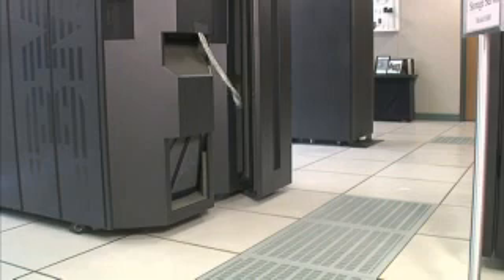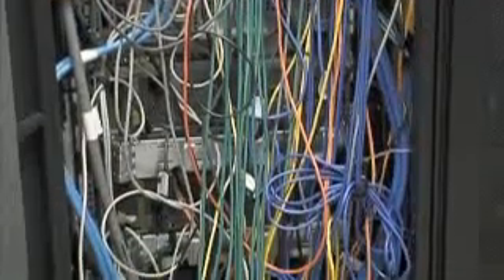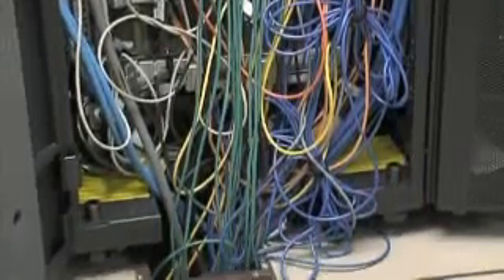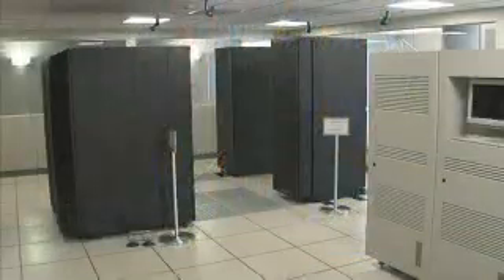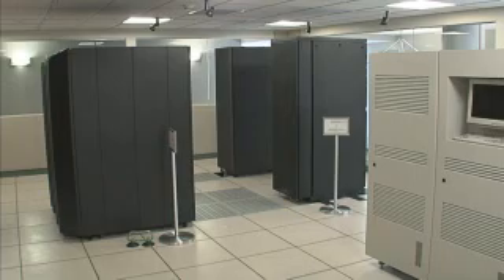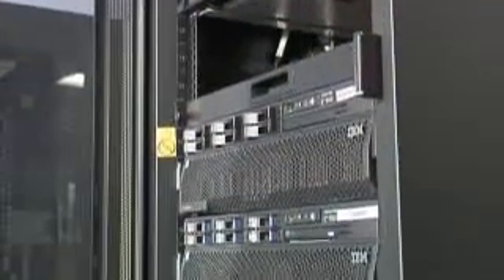Once we started analyzing the floor, we realized that by laying it out as a showroom, we had inadvertently created a lot of bad practices. The rows of machines in the front were actually exhausting heat into perforated tiles in the back, where additional machines would then try to use that for cooling. In addition, we had done poor cable management as well as other things in the raised floor itself. The racks were not laid out correctly. We had gaps in the racks in between them, as well as in between the machines in the racks. What this did was it allowed for the air to intermix from the front to the back, and this is what gave us a room that was extremely hot.